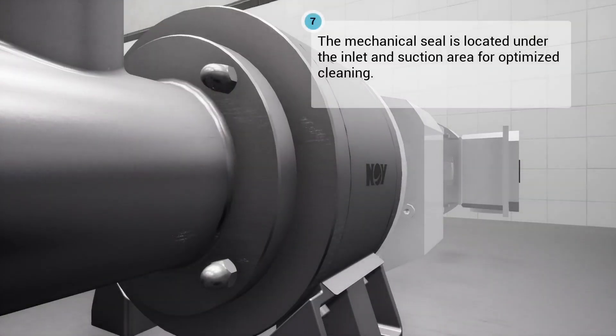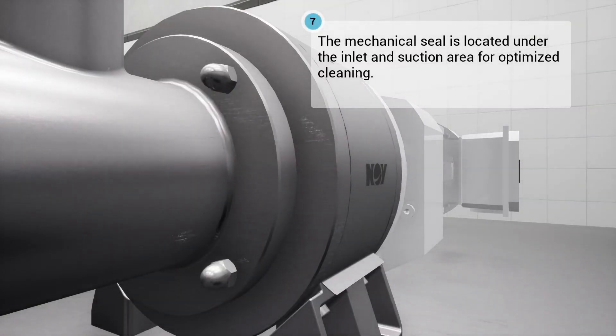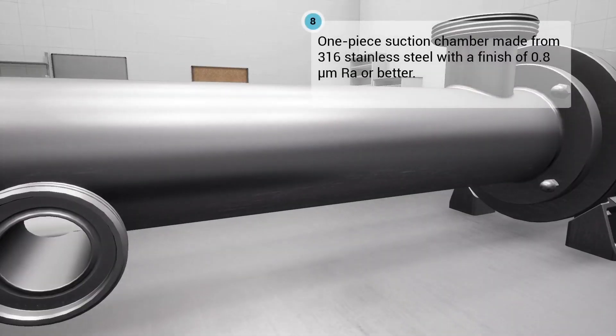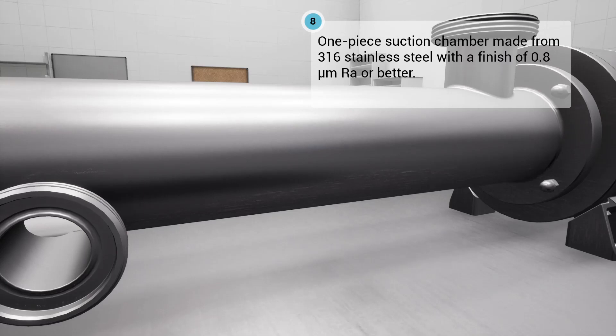The mechanical seal is located under the suction area for optimized cleaning and hygiene. One-piece suction chamber made from 316 stainless steel, with a finish of 0.8 micron roughness average or better.